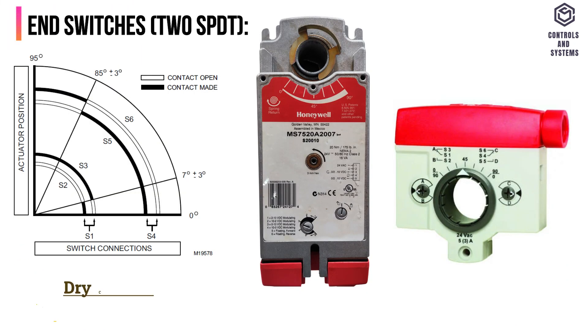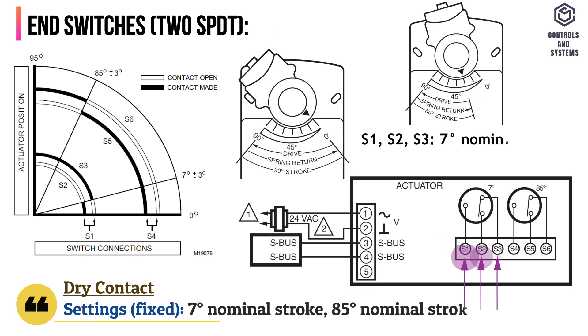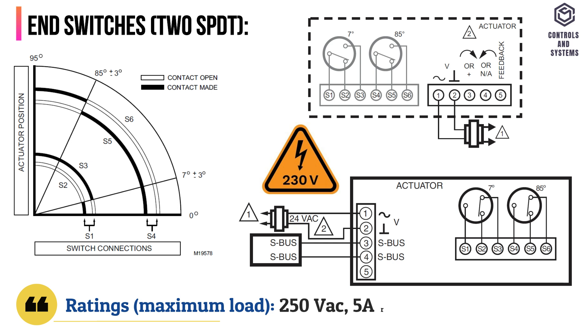End switches, dry contact settings, fixed: S1, S2, and S3 are for a 7 degrees nominal stroke; S4, S5, and S6 are for an 85 degrees nominal stroke. Ratings — maximum load is 250 volt AC, 5 amps resistive.